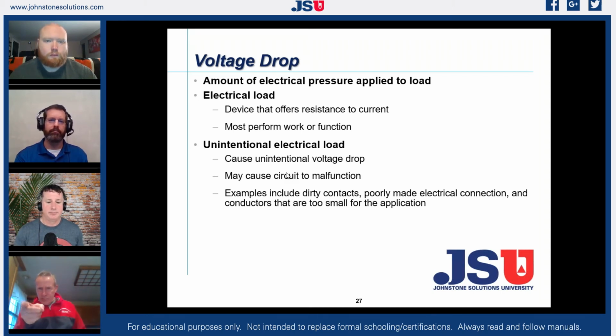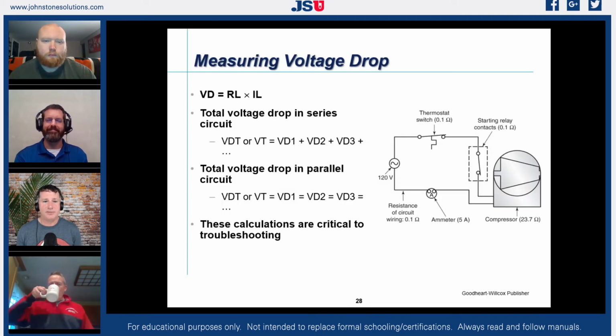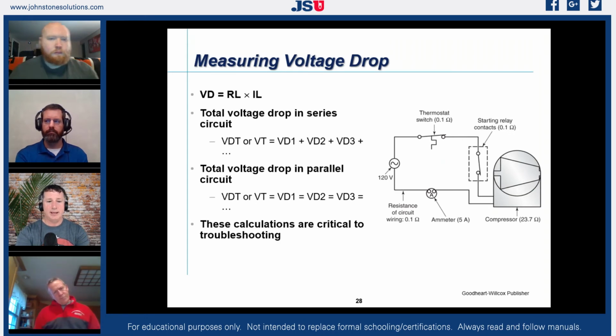Well, you should change contactors on your spring specials. Contactors are a wear item. It's up to us to decipher how far into that circuit we actually are. And this is basically the same kind of principle. If we look at measuring voltage drop across the circuit, we know that we have a voltage coming into a circuit, and we know that we have voltage on the outlet side on our load. If we change the resistance of our load, we can change the applied voltage across that. And we actually measure that out in the field when we're doing long applications of conductors. We measure voltage drops across those to see how much we lose.